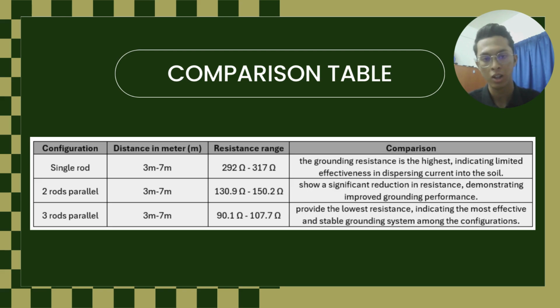And the last one is the three rod parallel setup. It is clearly our top performer. It provides the lowest and most stable resistance range, staying between 90.1 ohm and 107.7 ohm. In conclusion, for any installation requiring a high degree of safety and stability, the three-rod parallel configuration is the most effective choice for ensuring a reliable grounding system.